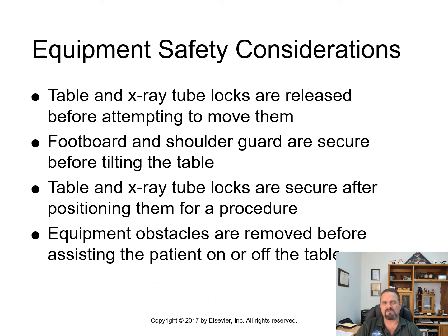All right, some equipment safety considerations. First off, the table and X-ray tube locks are released before attempting to move them. Don't try to force them. You may break something that's very costly. Footboard and the shoulder guard are secured before tilting the table. You don't want patients sliding off your table because you're adjusting the table to the upright position. Table and X-ray tube locks are secure after positioning for the procedure. So make sure that the table and the tubes are locked into place before you actually do it.